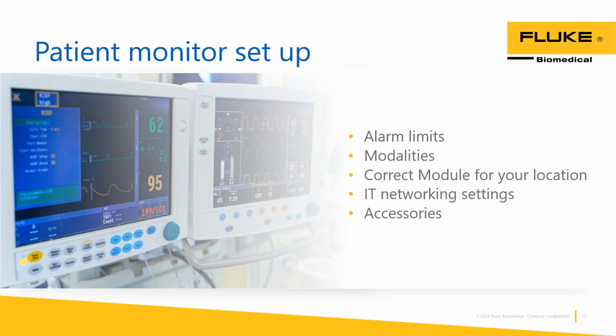A lot of them have built-in O-rings that will start to get dry and leak over time and start to bleed down more and throw off your bleed down rates. So another consideration with that is, are you using the accessories that are with that monitor? And I know a lot of people now are using a lot of disposables. Do we have the right disposables with it as well? So just some considerations as we're talking about this monitor setup.